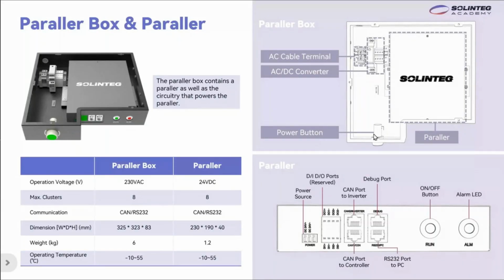The circuit includes an AC cable terminal and AC-DC converter. The parallel unit needs 24-volt DC, but the parallel box is designed to connect with the backup side, which is 230-volt AC. So the circuit converts AC to DC and steps down the voltage from 230 to 24 volts, then supplies power to the parallel unit.